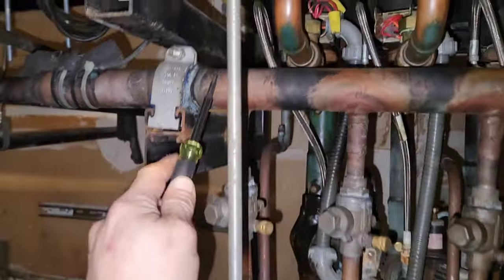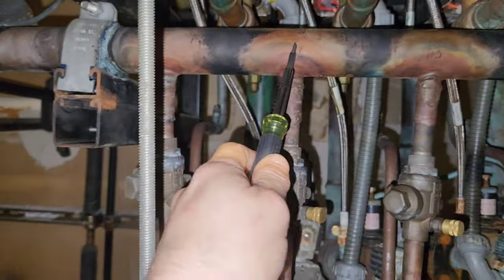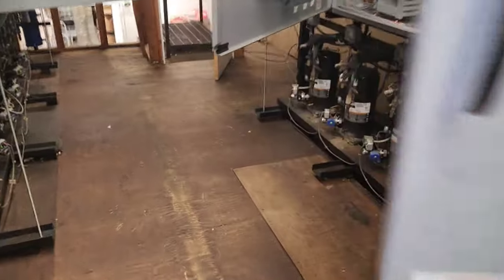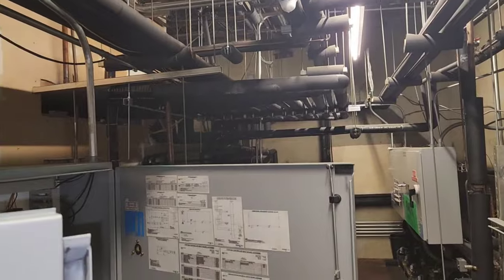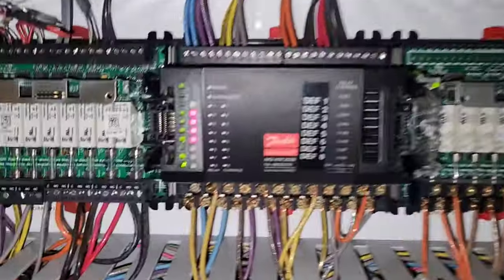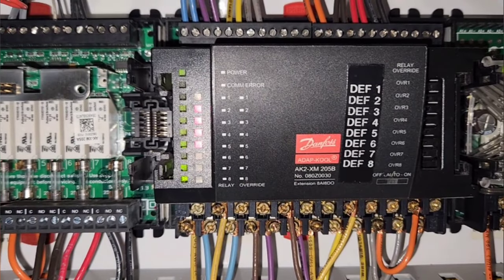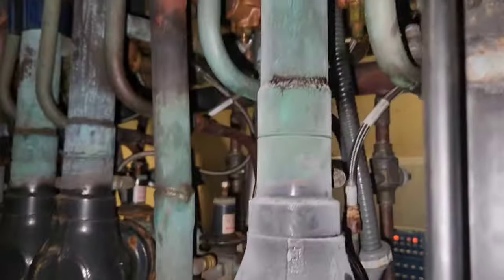Here's what I'm looking at — I got A1, which is part of that ice cream case, and then A2. When I energize A1 you can hear that, but A2 doesn't do that. I've got them bypassed here, switched over. I later learned that this was not a good idea, because 6 of my 8 compressors went into thermal overload.